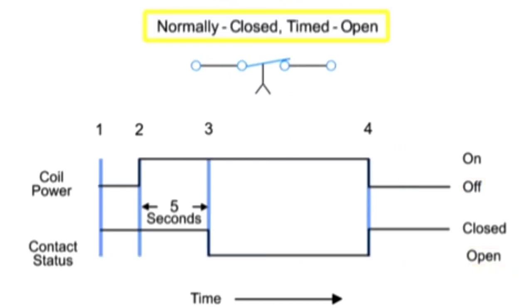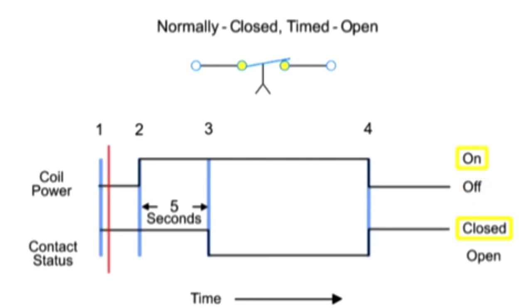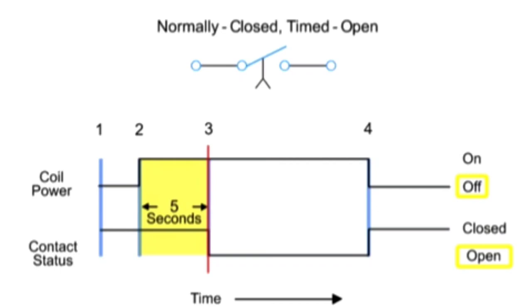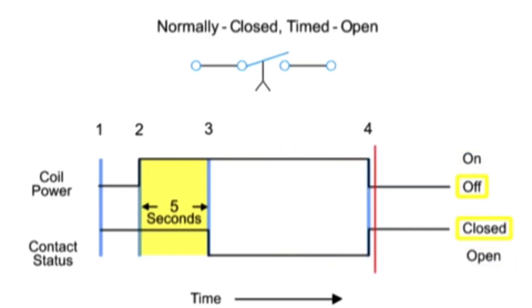Next, we have the normally closed, timed open contact. This type of contact is normally closed when the coil is unpowered or de-energized. The contact is opened with the application of power to the relay coil, but only after the coil has been continuously powered for the specified amount of time — in this case, five seconds. Thus, the contacts open five seconds after the coil is energized and close immediately when the coil is de-energized.